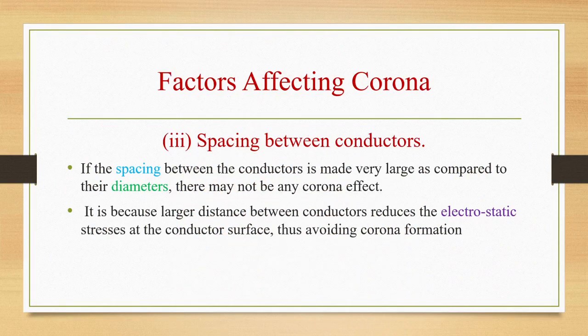Spacing between conductors. If the spacing between the conductors is made very large as compared to the diameters, there may not be any corona effect. So spacing between conductors also plays a major role in the formation of corona. If the spacing between the conductors is made very large as compared to the diameters, then there may not be any corona effect. It is because a larger distance between conductors will reduce the electrostatic stresses at the conductor surface and thus corona formation can be avoided.